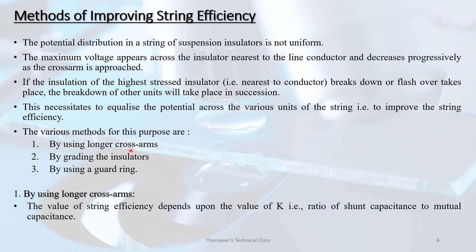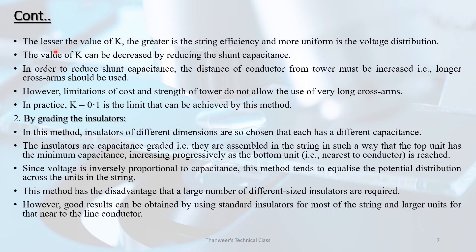Methods of improving string efficiency: By using longer cross-arms — the value of string efficiency depends upon the value of K, the ratio of shunt capacitance to mutual capacitance. The lesser the value of K, the greater is the string efficiency. The value of K can be decreased by reducing the shunt capacitance by increasing the distance of the conductor from the tower, i.e., using longer cross-arms. In practice, K equal to 0.1 is the limit achievable by this method.